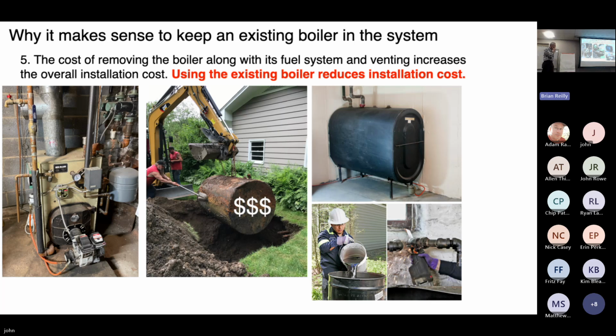The cost of removing the boiler. If the boiler is functional, and this is a cast iron boiler, I'm sure you've seen many cast iron boilers. One thing I will say about cast iron boilers is they can last a long time, if reasonably maintained. We've seen cast iron boilers running that are probably close to 100 years old. Now, that's pushing it, but 20, 30 years is common. I've got 2 cast iron boilers that are both about 25 years old, and they look brand new. Every year we change the nozzle, clean it, and put new filters on it, and there's not a lot going on inside the boiler. This is where most of the action is, right here at the burner.